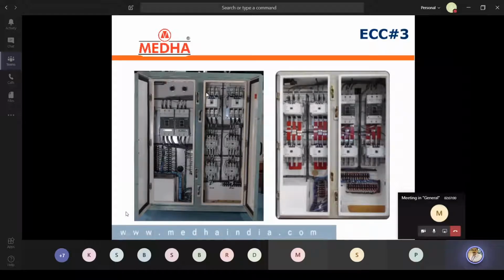Why these 2 contactors: first of all, this contactor shorts the internal winding from series to Y parallel connection to make the path, because the input operating voltage is same, but the fan should run at higher speed for fast operation. So internally the system, by energizing this contactor, changes the winding connection from series to parallel, so that resistance will decrease, current will increase, and accordingly speed also will increase. So similarly number 1 fan and number 2 fan. Actually these are 150 ampere contactors and this is 325 ampere contactors.